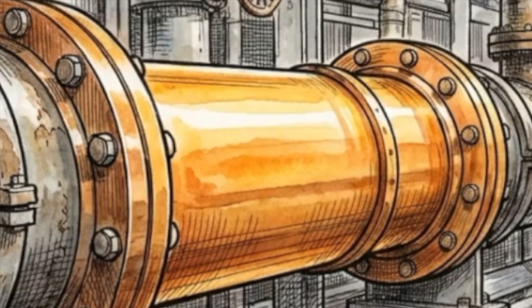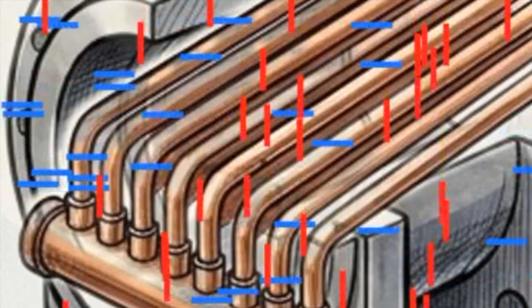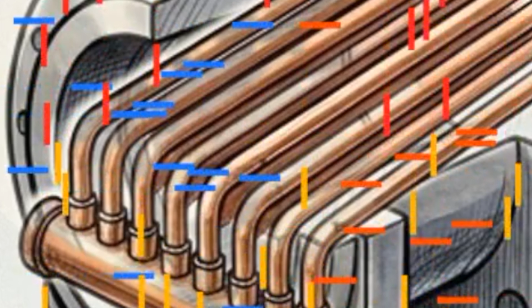The mechanical correction is straightforward. You install a desuperheater. This is a targeted heat exchanger placed directly on the discharge line to intercept the gas. In this cross-section, superheated red gas crosses pipes carrying cold blue water. Zooming in, thermal energy pushes through the copper barrier. The blue water absorbs the heat, becoming a warm amber flow. Zooming out, the gas exits cooled, generating continuous free hot water.